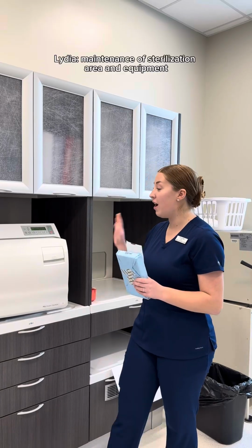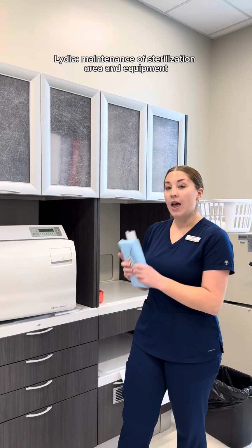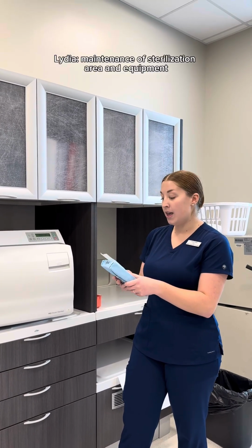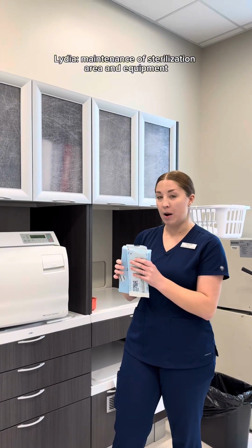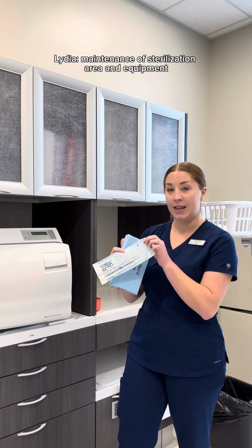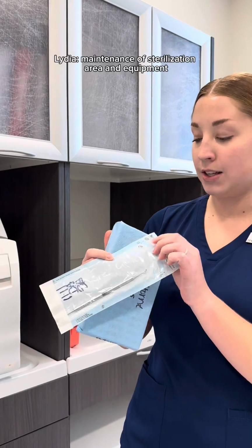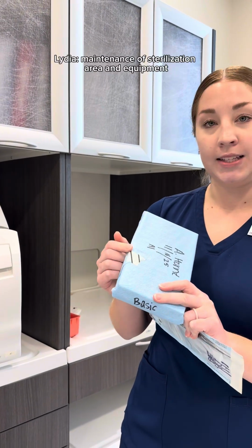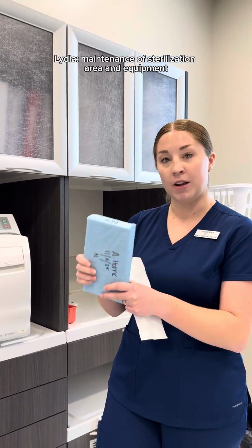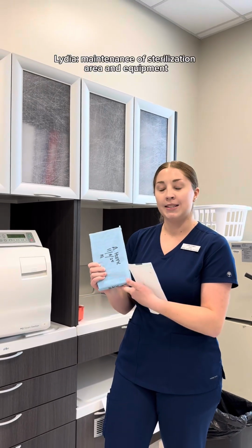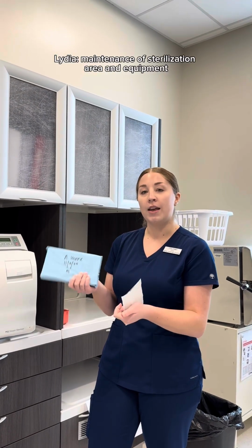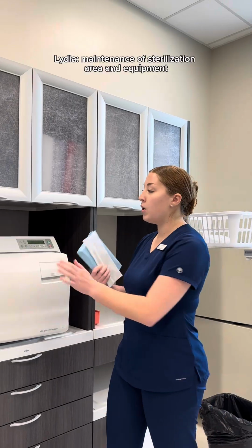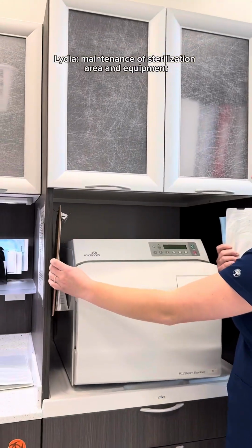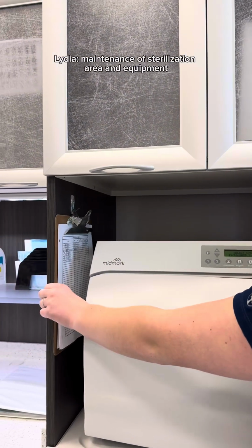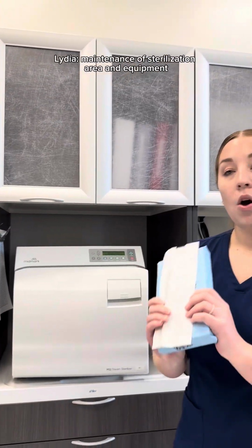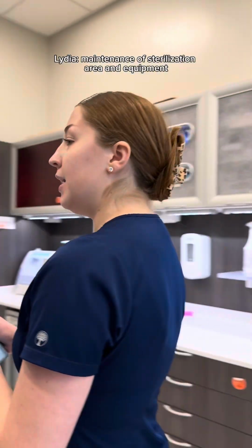Okay, so once the autoclave has finished its cycle, the instruments are then ready to be put away. You want to check and make sure that they have reached the proper temperature by looking at the indicators, both internal and external. And then on your cassettes, you can check the tape, make sure it has the diagonal lines showing it reached the proper temperature. And then on the inside, it has the internal indicator that you'll look at when you open it. You also want to log on our sterilization log right here that everything has reached the proper temperature and that it passed. Once you've done that, you can go ahead and put your instruments away.